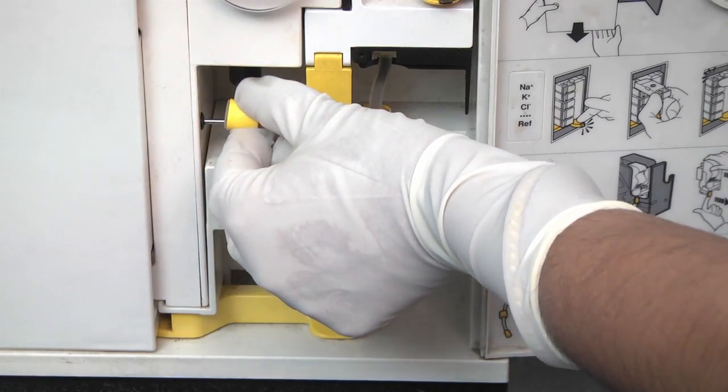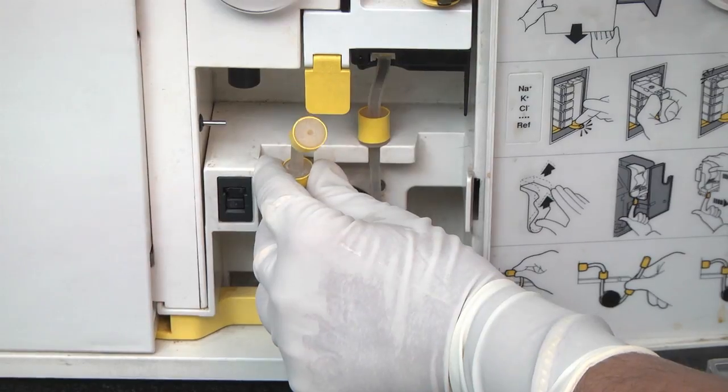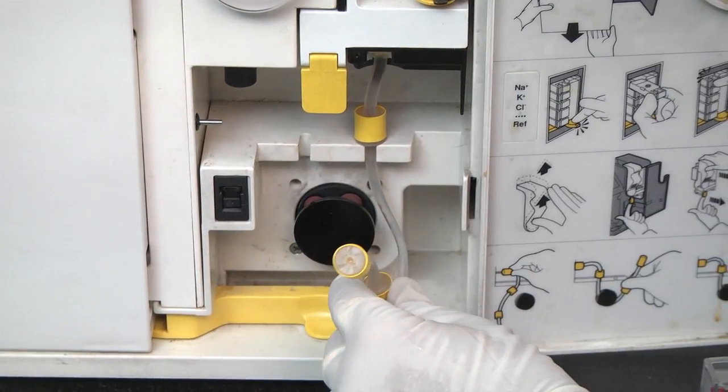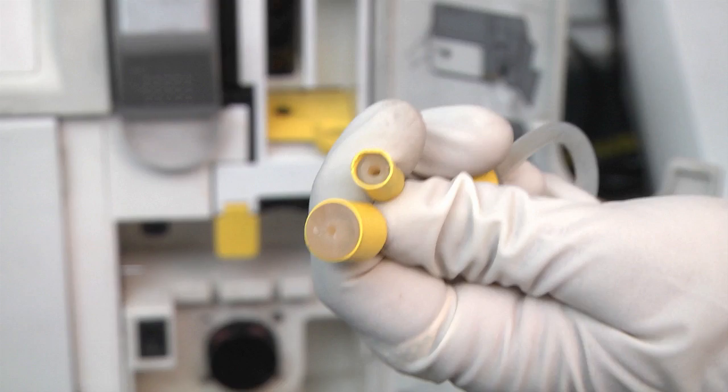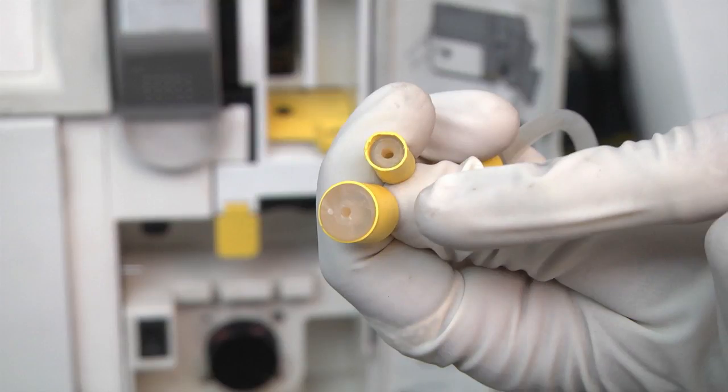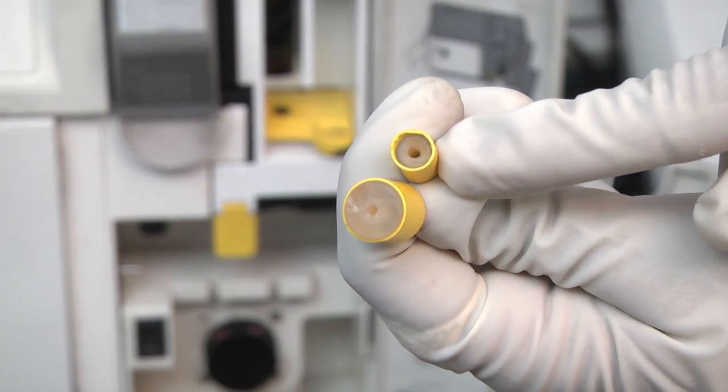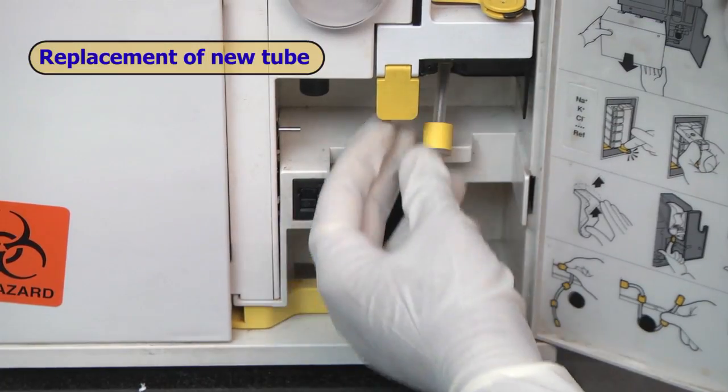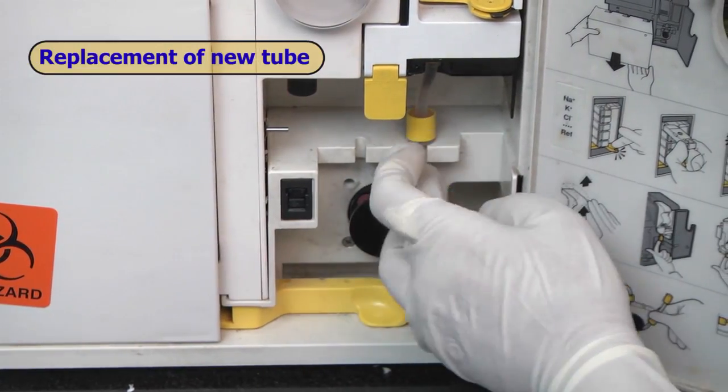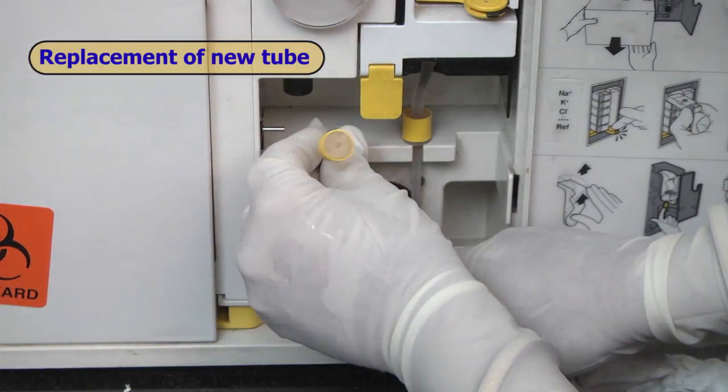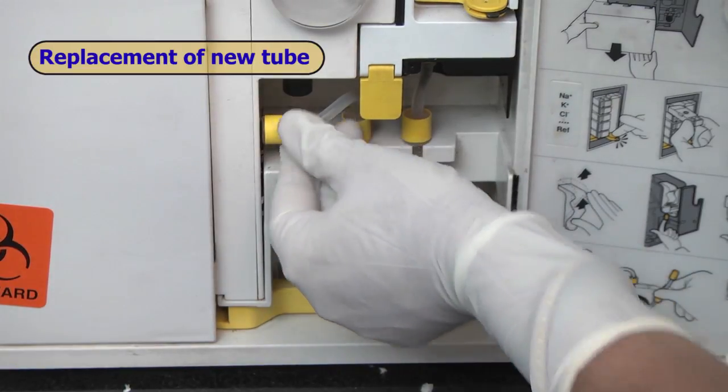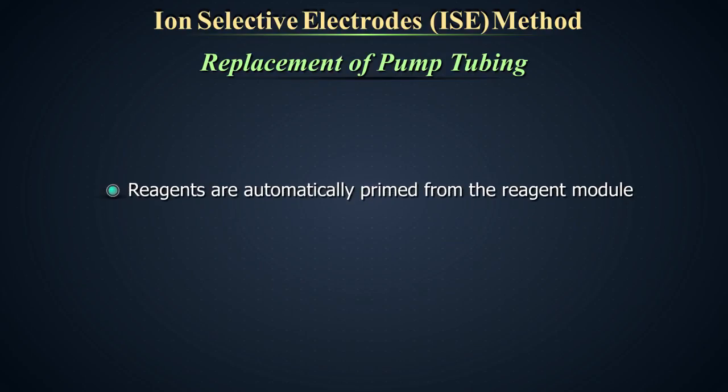Carefully remove the tube beginning from the collar on the left and then the collar on the right. The pump tube has a large collar on one end and a small collar on the other. Fix the large collar first, then fix it through the groove in the pump shelf. Bring it around the pump, then through the groove of the pump shelf again and finally fix the small collar. Reagents will be automatically primed from the reagent module. It is necessary to recalibrate when replacement is complete.